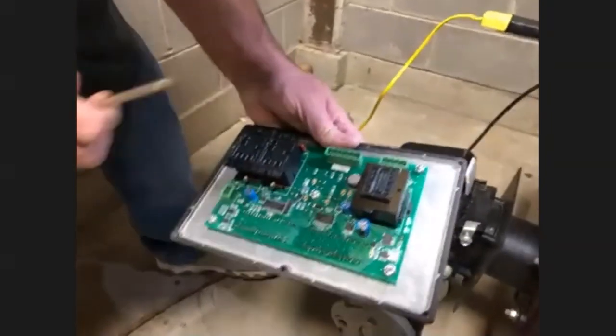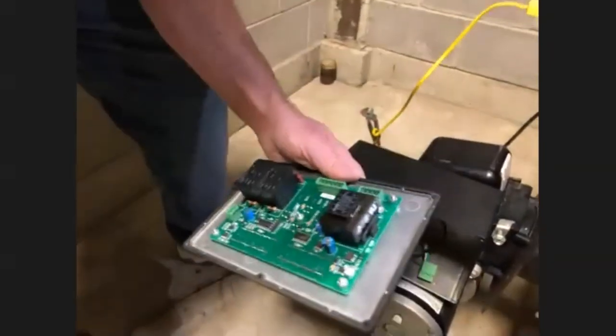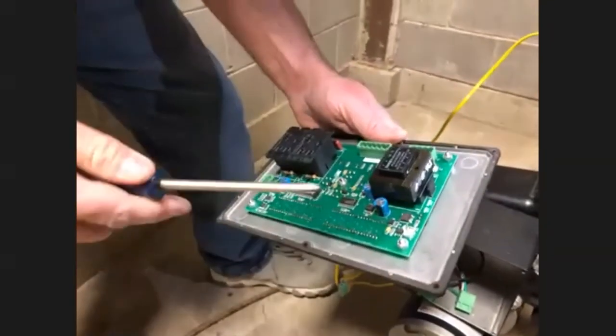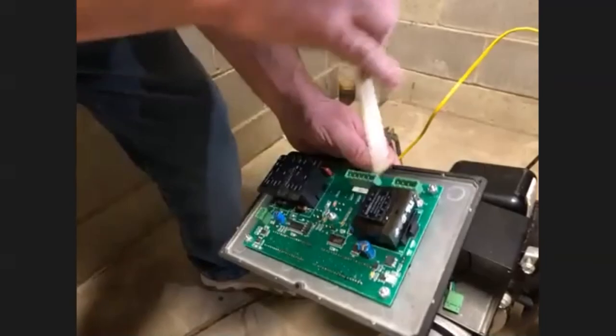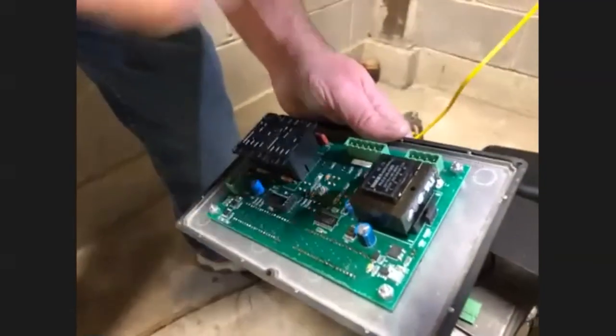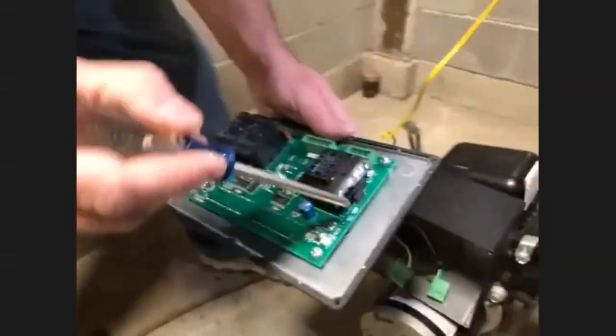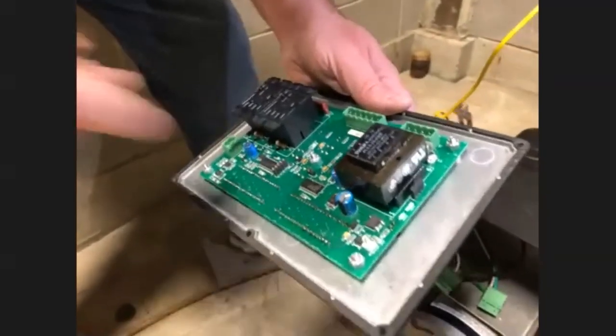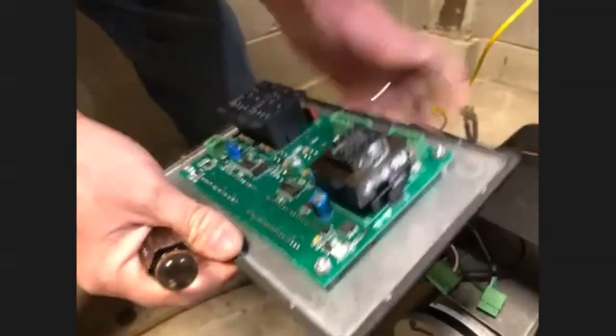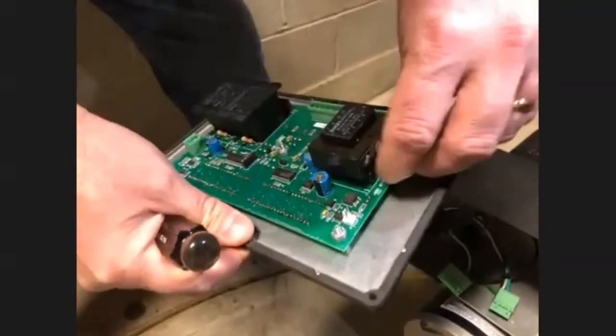And since we do have this open, another thing to remember: when these units are shipped, whether you buy 110 volt or 220 volt, there are jumpers right here. If you see on the board, it tells you how to set it up for either voltage. If you need to change it, you can set it accordingly. Right here, we have it set up for 110.